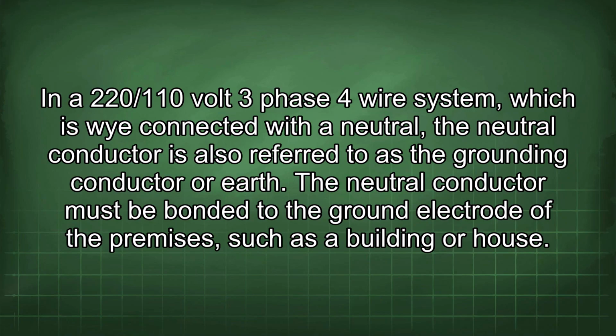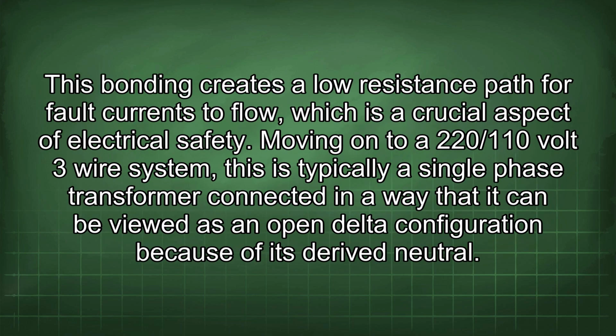In a 220/110-volt 3-phase 4-wire system which is Y-connected with a neutral, the neutral conductor is also referred to as the grounding conductor or earth. The neutral conductor must be bonded to the ground electrode of the premises, such as a building or house. This bonding creates a low resistance path for fault currents to flow, which is a crucial aspect of electrical safety.